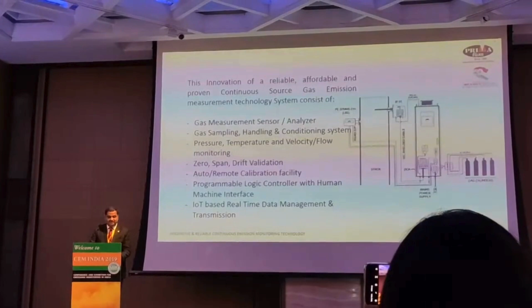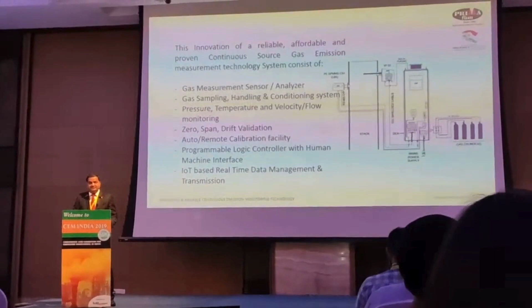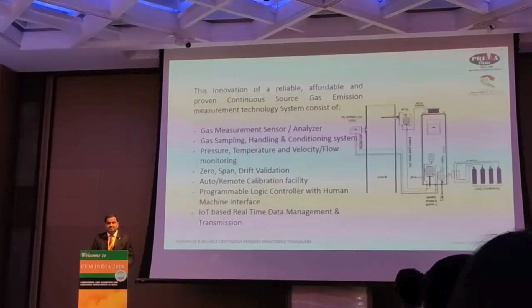The innovation of reliability with this technology is that the system consists of a gas measurement sensor, an analyzer, and a gas sampling, handling and conditioning system. As I mentioned, it includes pressure, temperature, velocity and flow measurement, and zero and span drift validation. That is the most important thing we carry out before we do all this. We have incorporated remote and auto calibration facility, integrated into the system.